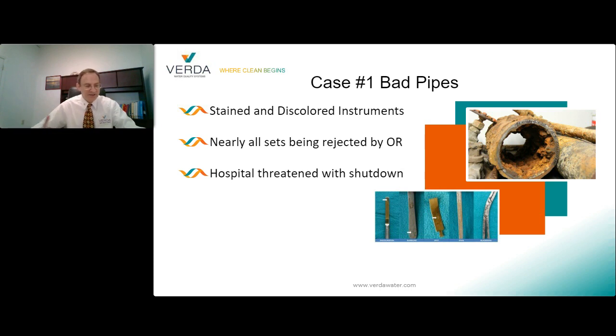So the hospital started their analysis with the water and worked their way one step at a time to the sterilized instruments. Eventually, they pinpointed the source of the issue: steam feed water. The facility was using plant or facility steam, and while the quality of steam was adequate for non-critical uses, it wasn't for sterile reprocessing. The steam quality, previously adequate, had become marginal, and the repair work on those water lines was just enough to cause major havoc inside the hospital.